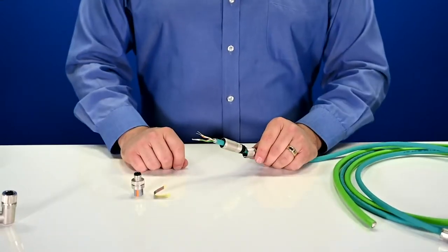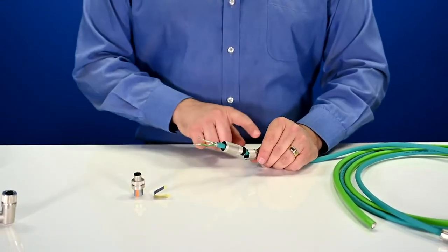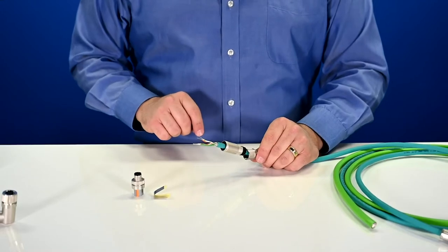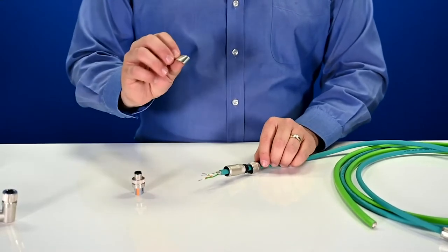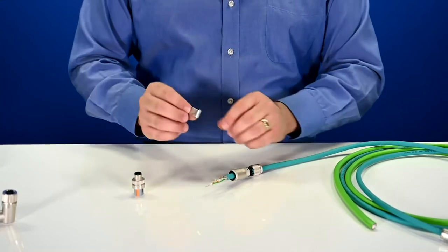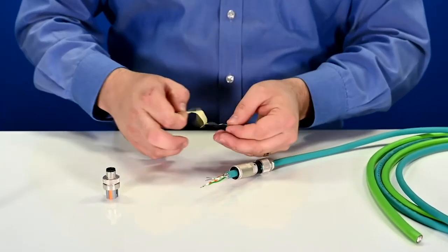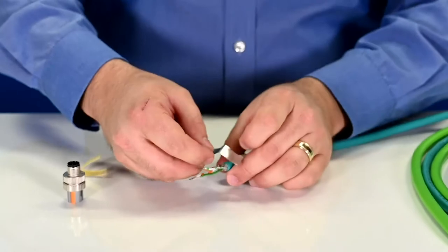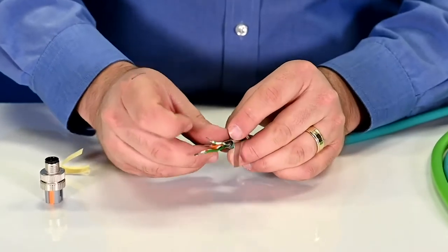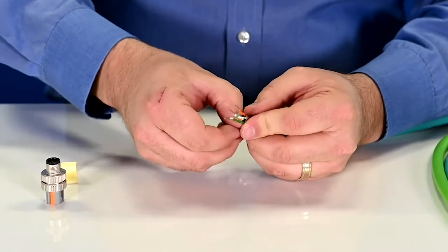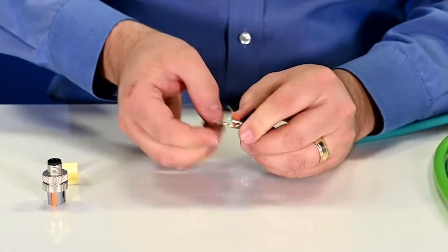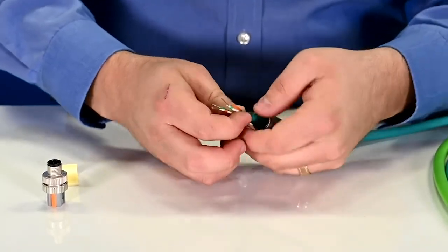Now that we have our cable prepared to terminate, we have our back shell installed on the cable. The next step is to prepare the shield. All of these connectors come with a little strip of metallic tape, and all you have to do is take that tape off of its housing and wrap it around the shield that you have exposed on the cable. This is going to make sure that shield doesn't come unraveled as we tighten down the housing. So we'll go ahead and install that.